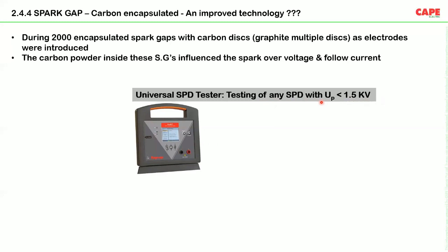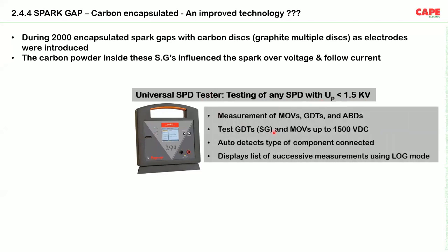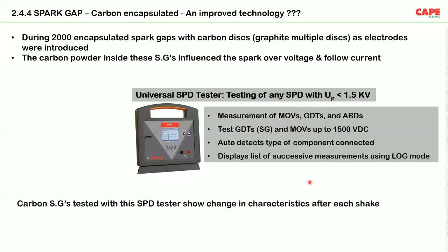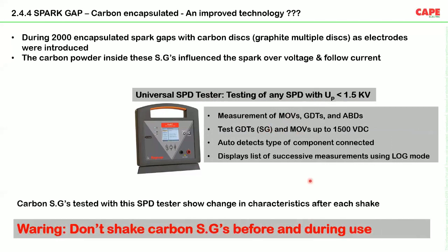If you shake the SPD on the right side, probably the voltage protection level is 1 kV. If you shake it on the left side, probably the voltage is 2 kV. So it keeps on changing. Such devices are also sold in the market. Please be very careful. We were always trying to write that if you are using these kinds of spark gaps, don't shake the spark gap, because if you shake it, its parameter will change because of the carbon powder.